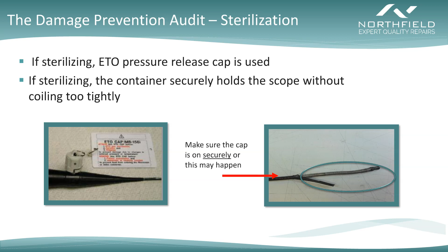before the scope goes into the sterilizer. Now, if you're using a different container than what the scope came in, I've seen many facilities go from sort of the OEM supplied plastic containers to a more rigid container. That's totally fine. You just need to make sure that that scope is still secured properly inside that basket and in a way that doesn't cause it to kink up or coil too tightly. If you don't have the scope secured in a proper way, the scope will slide around during the transportation process. I know I've seen many technicians, as they're pulling for cases, they are in a hurry, they're moving quickly, and they tend to pull those containers off the shelf very quickly. And if that scope is not held in place tightly, that scope is just getting banged around left and right inside that container. So again, that's going to be a lot of damage that could have been prevented just simply by making sure that the scope is secured properly inside the container.